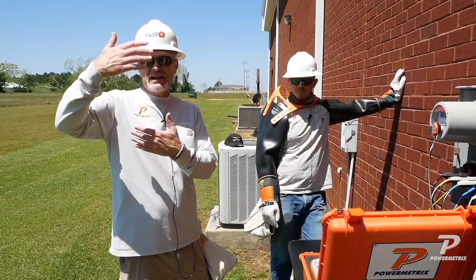So this is exactly what we do out in the field. We look for these problems, and by changing all of this out, we don't think that's any of our connections between here and there. And the machine tested A and C correctly and it tested those fine. So I'm not thinking it's the gear, I'm thinking it's the B phase CT. So this would be a site where you would have somebody take a look and maybe change that B phase CT and see if that doesn't correct the problem. So we may have found an issue here at this site according to what the machine's saying. Wouldn't you agree? Yep. Yep. All right, because that's why we're out here, right, is to find these issues.